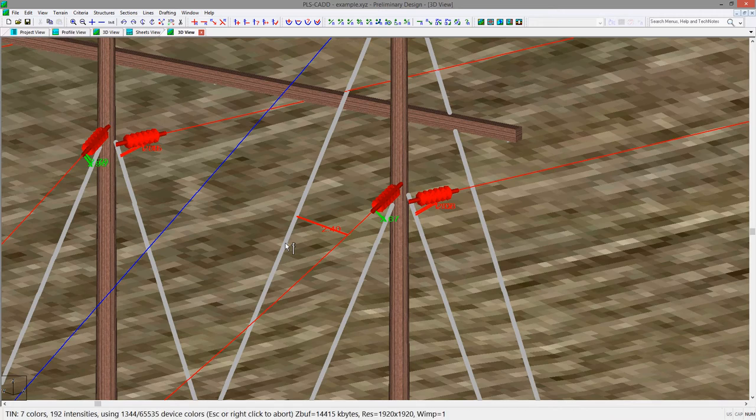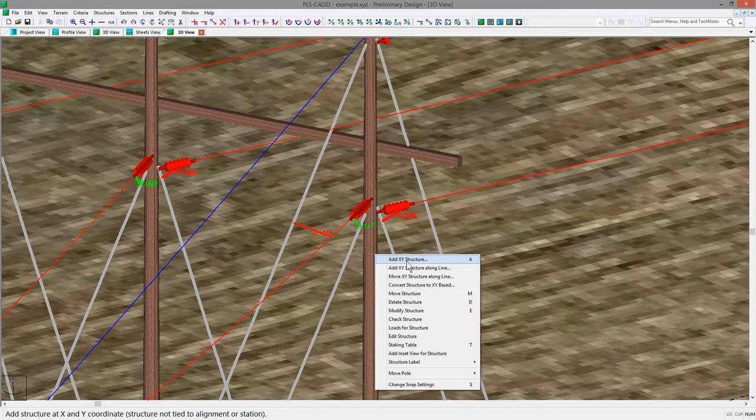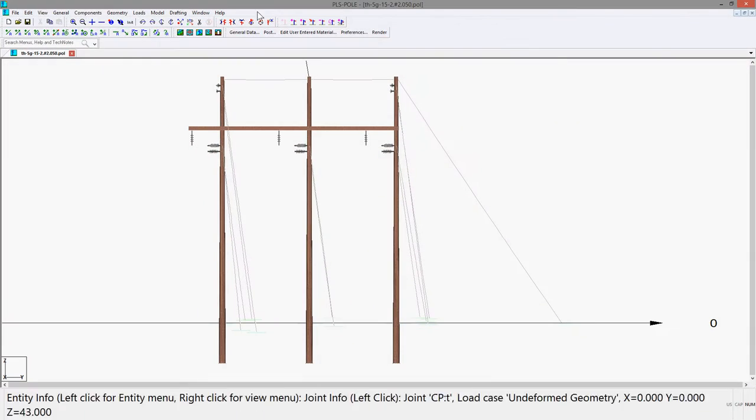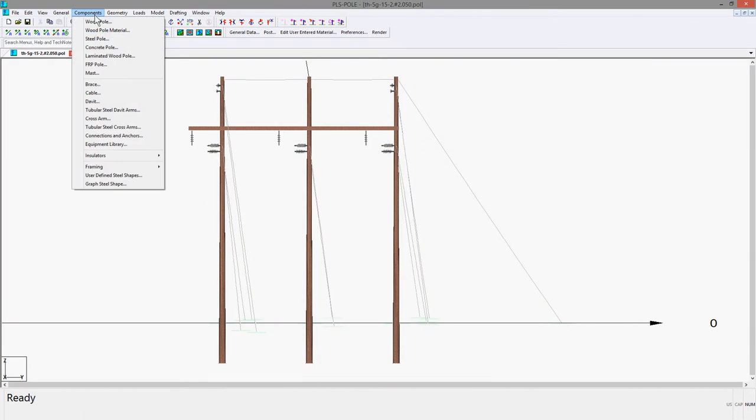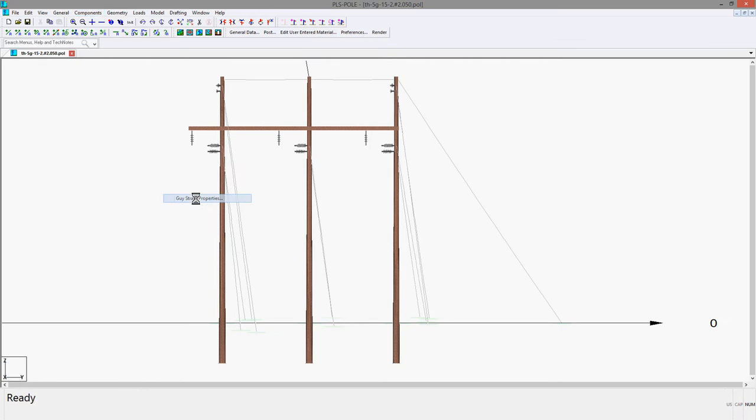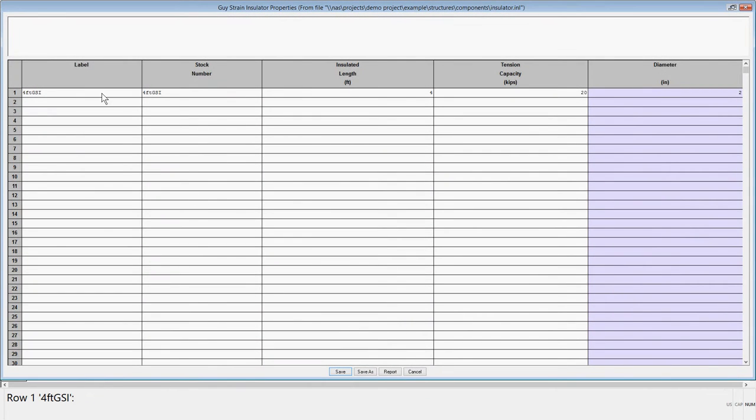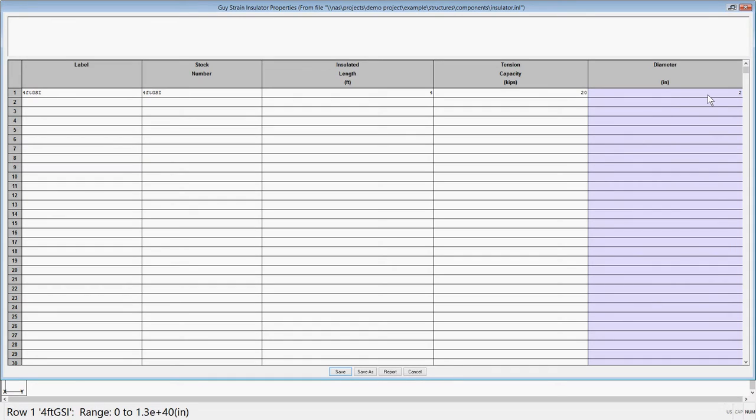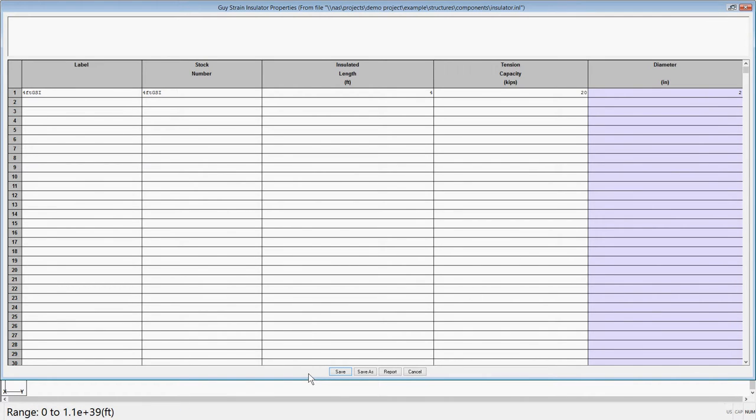First, you will want to edit the structure, and we can go to the components, insulators, guy strain properties where you can input the guy strain information you wish to use. For this example, we will use a 4 foot guy strain insulator, and I have given it a 4 foot length with a tension capacity of 20 kips. The diameter column can be input to properly display the guise strain in line with the guy wire. For this model, I will use a 2 inch diameter rod.